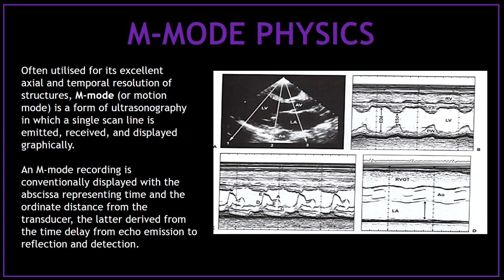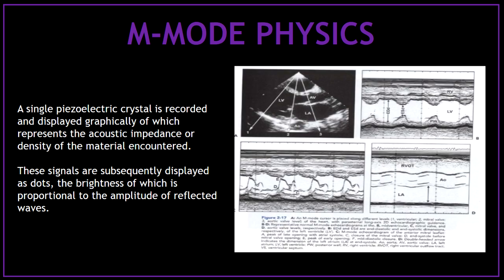Now let's talk about the M-mode physics. Often utilized for its excellent axial and temporal resolution of structures, M-mode is a form of ultrasonography in which a single scan line is emitted, received, and displayed graphically. An M-mode recording is conventionally displayed with the abscissa representing time and the ordinate representing distance from the transducer, the latter derived from the time delay from echo emission to reflection and detection. These signals are displayed as dots, the brightness of which is proportional to the amplitude of the reflected waves.